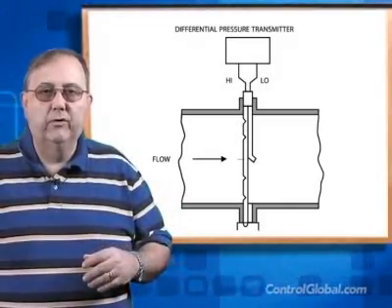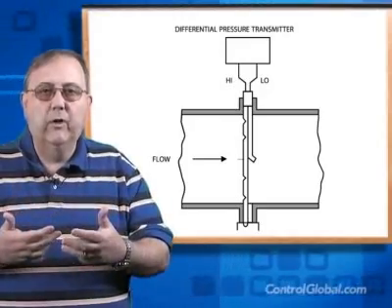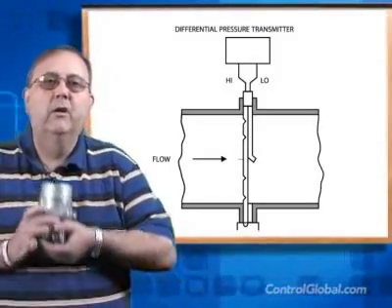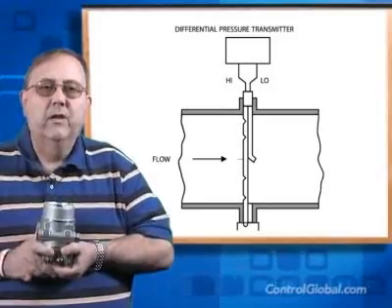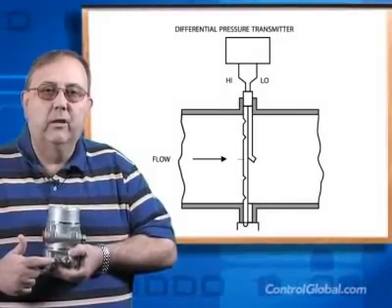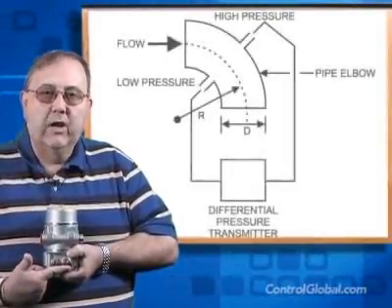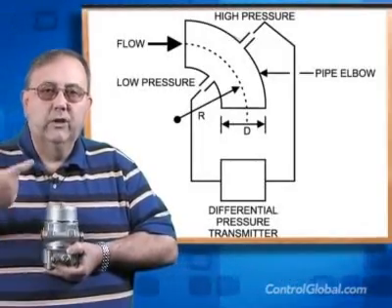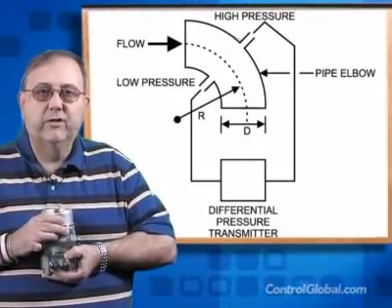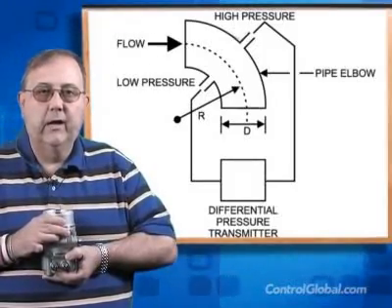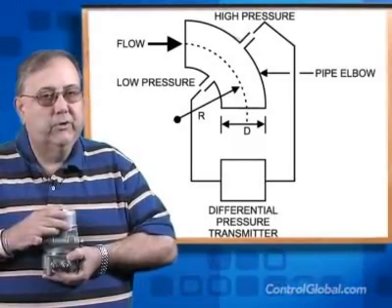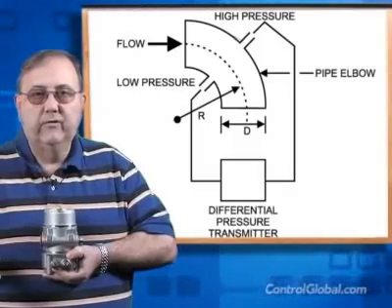Some additional kinds of primary flow tubes, such as laminar flow tubes and critical flow elements, don't follow this rule, but they are exceptions. The other part of a differential pressure flow meter is the differential pressure transmitter itself. The upstream and downstream pressures from the primary flow elements are piped from the taps on the element to ports on the differential pressure transmitter. The transmitter measures these pressures, computes the differential between them, and usually has an integral flow computer that extracts the flow value from the square root of the differential, and produces a linear analog output — usually 4 to 20 milliamps DC — and/or a digital output such as HART, Foundation Fieldbus, or Profibus.